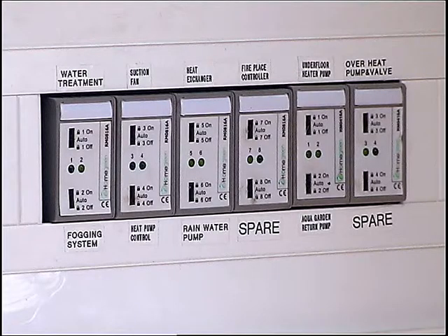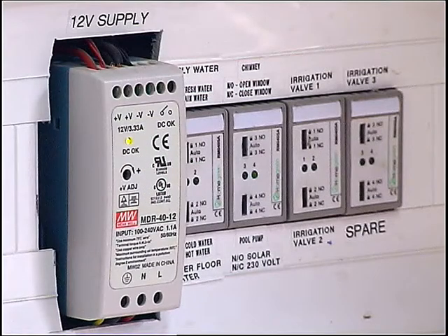One example is we'll always make sure that the toilets have sufficient water by making sure there's a pump switched on and running to provide water to the house. The irrigation runs off the same tank, and the irrigation is on a timer. We'll only switch on the irrigation if there's sufficient water. As the tank level drops and it reaches a certain percentage, we'll switch off the irrigation to make sure we've got water available for all other services.